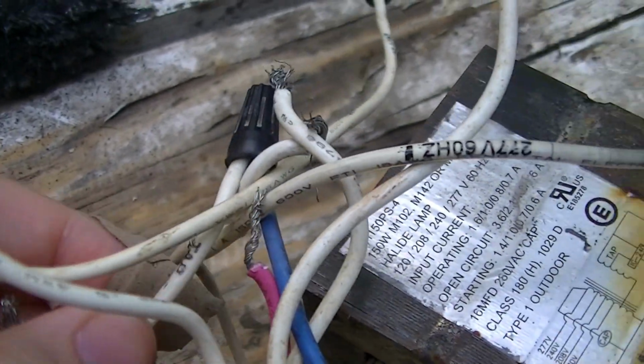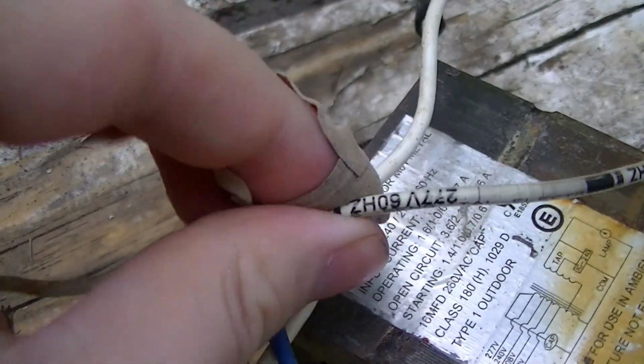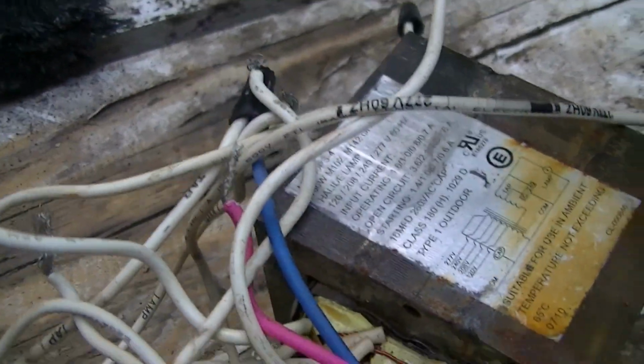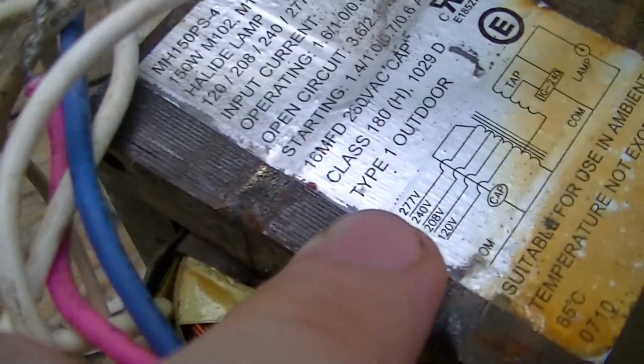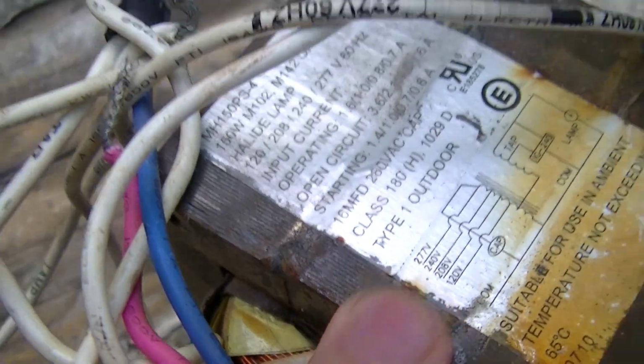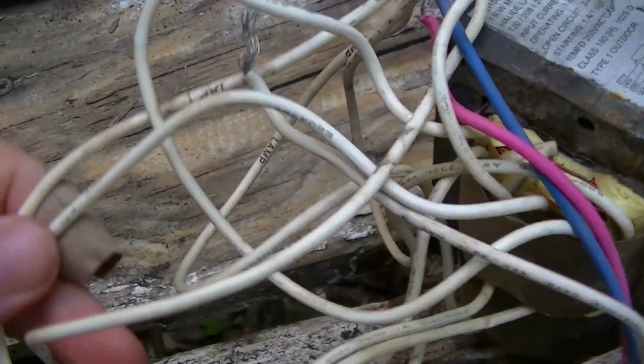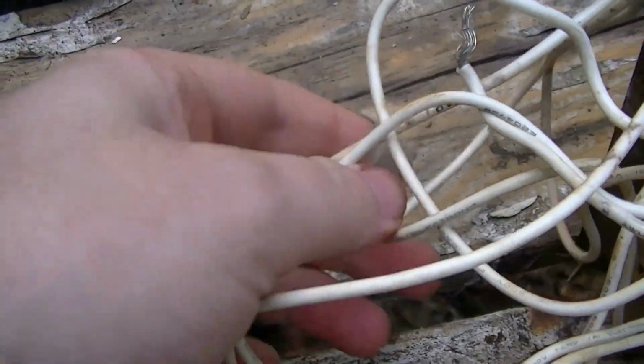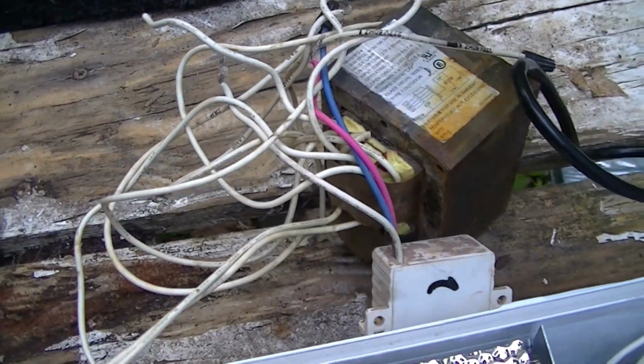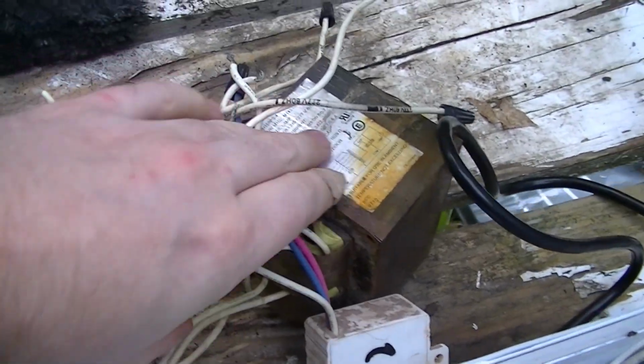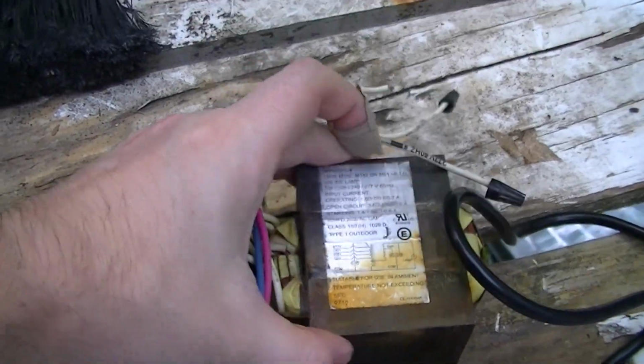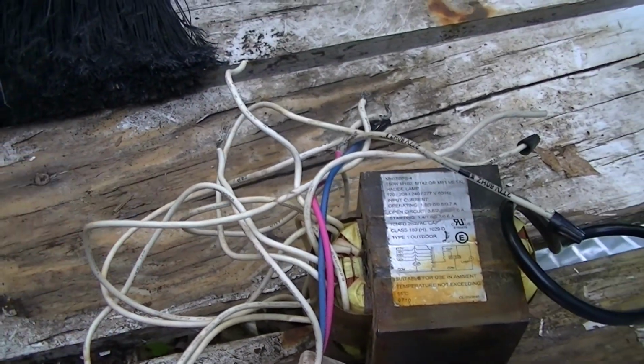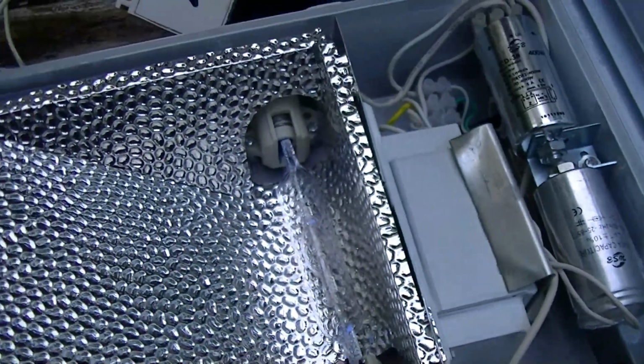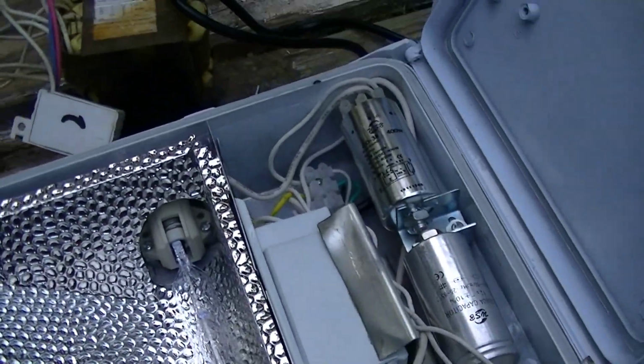So things like the igniter tap there, this is the 277 volt input because this is a quad tap, 120, 208, 240 or 277 volt ballast. Here's the lamp wire there. So even though the wires are all white, they're all marked with what they do, and a lot of ballasts aren't like this. Each wire can be a different color. So yeah, overall, quite simple internally.